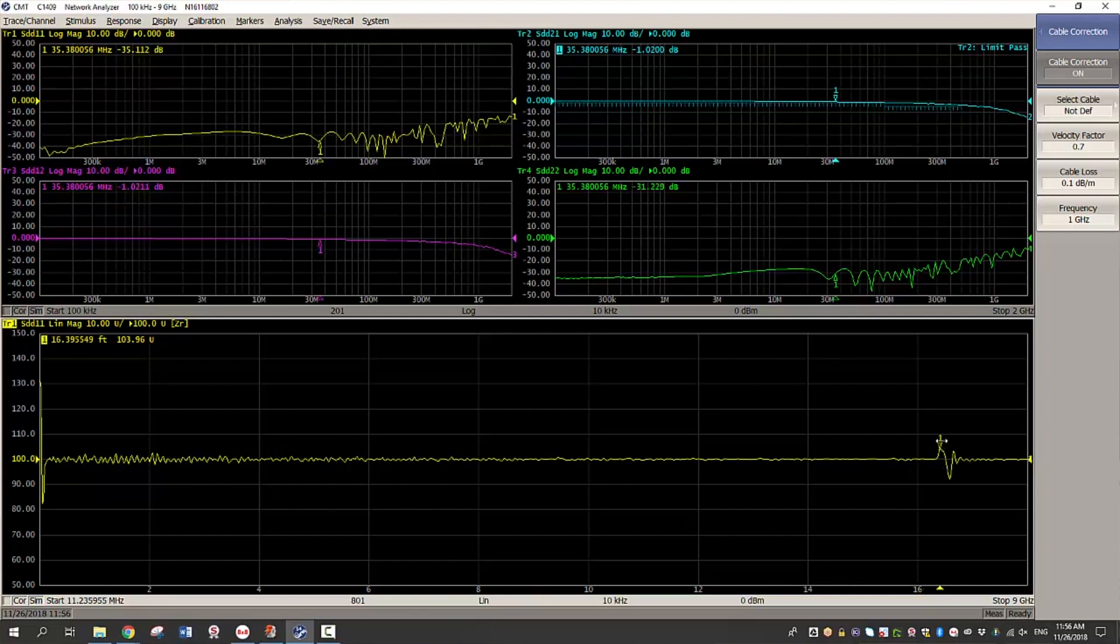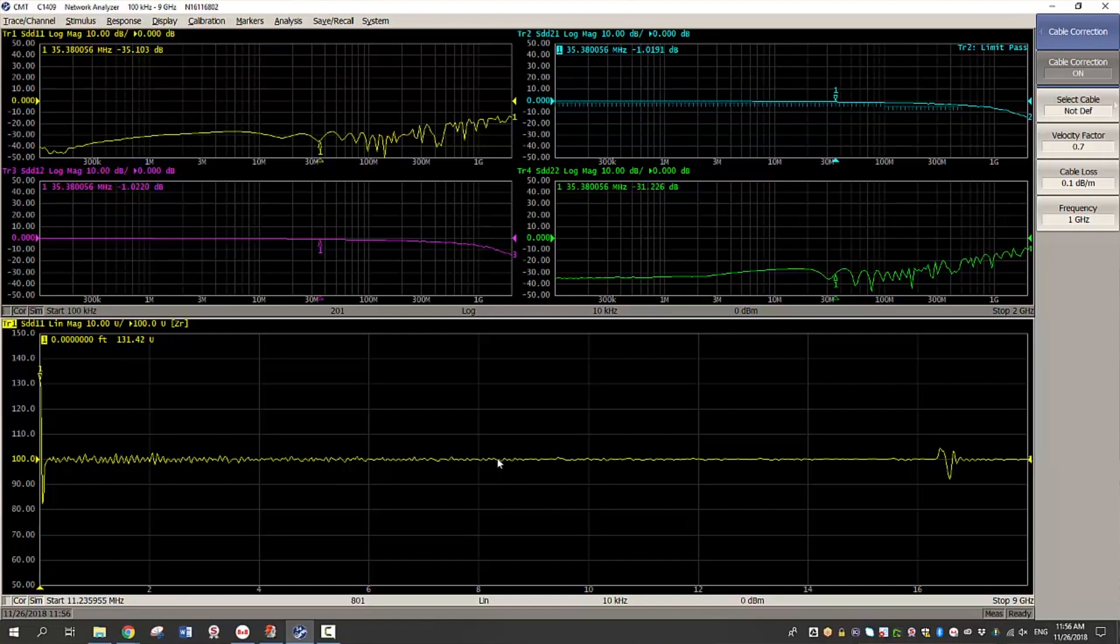So by adding a marker, I am able to see the mismatches. So this second mismatch is the end of the cable. And then the first bigger mismatch is the start of the cable. Suppose there was a significant fault detected in the cable, then it would appear as a larger bump along the distance.